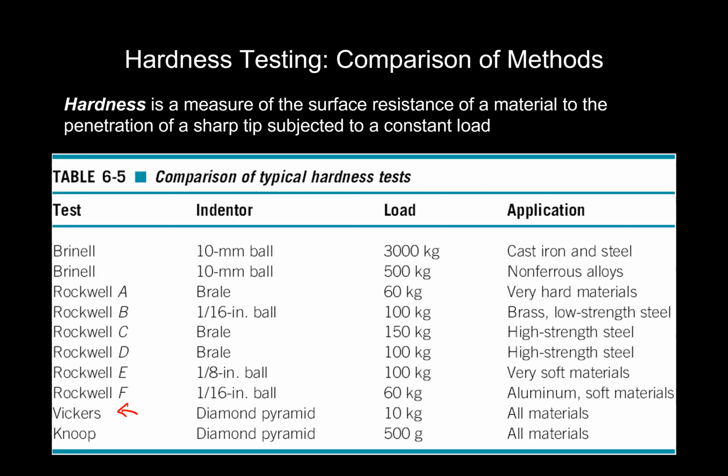And Rockwell is a little bit more sensitive to the type of material. So you'll have to adjust the type of Rockwell, the tip and the load you apply, function of the material. Okay. So it requires a little bit of expertise when you use Rockwell or understanding of the material you are testing.